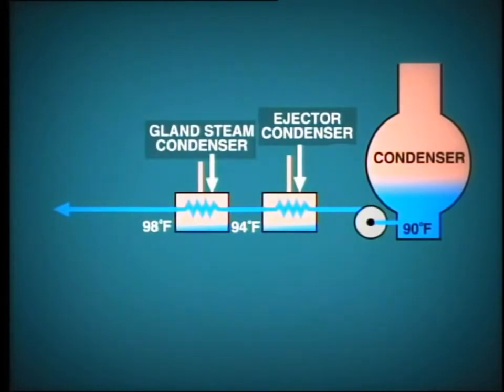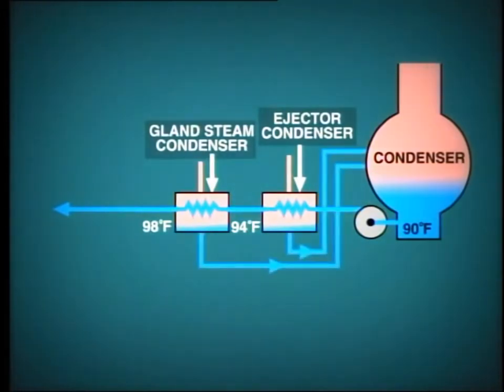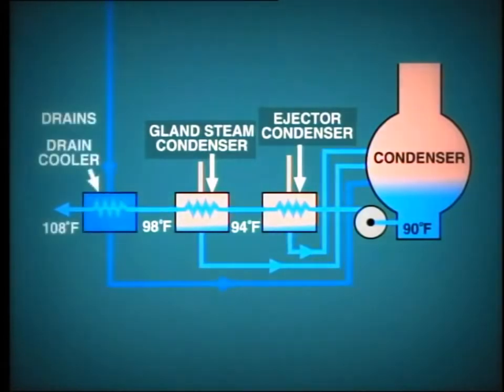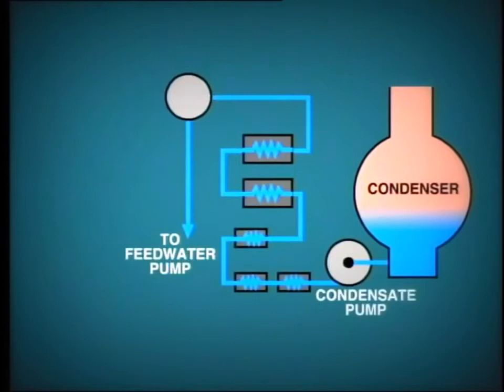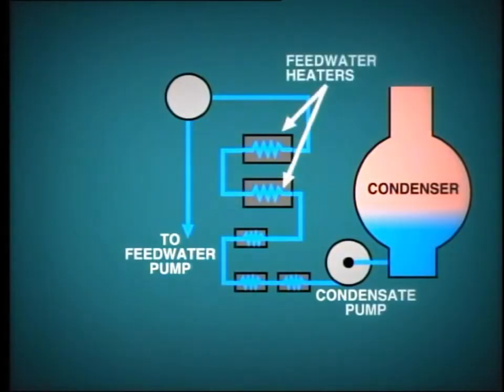The condensed steam is then routed back to the condenser hot well. A drain cooler is often located here and uses condensate to extract heat from water returning in the heater drains. The condensate then passes through several feedwater heaters where heat is added by extraction steam. In this particular scheme shown here, we have two closed-type heaters and one open heater where the extraction steam comes into contact with the condensate.